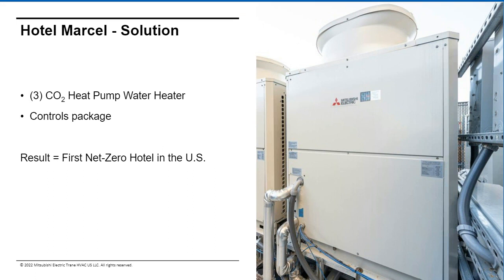So what we have for this whole building is 3 hot water heat pumps. This is a picture of one installed up on the roof. It has a control package and all those different accessories that we talked about: storage tanks and swing tanks and pumps, heat exchangers. But it's split up into 2 separate systems. One system serves the hotel rooms, and the other system serves more of the common areas. So it's 2 overall hydronic systems.